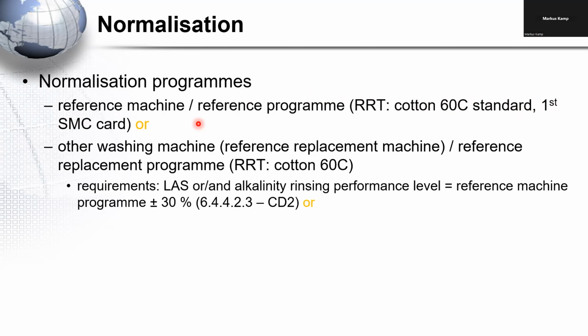Or the next option is that you use another washing machine, and I like to call it a reference replacement machine with a special replacement program, because it has to fulfill special requirements regarding the rinsing performance. So the LAS or alkalinity rinsing performance, depending on what you are testing in the test series, has to be on the same level as the reference machine, plus minus the given tolerance here. That means in advance, you have to run some test series in your lab where you compare this replacement machine in relation to the reference machine, so that it has the required rinsing performance.